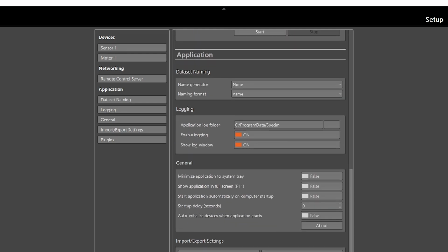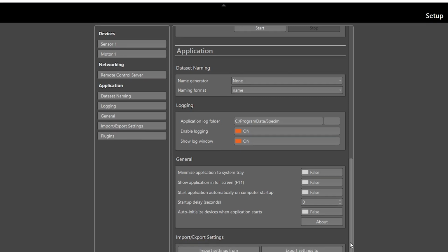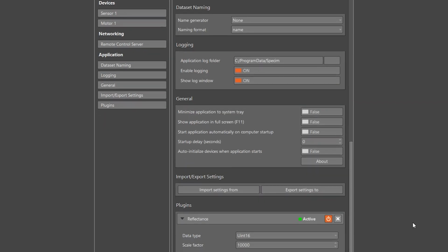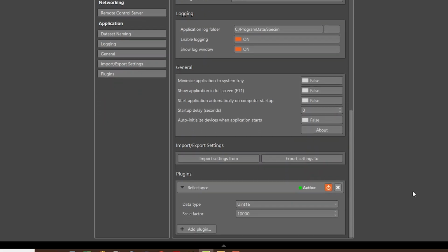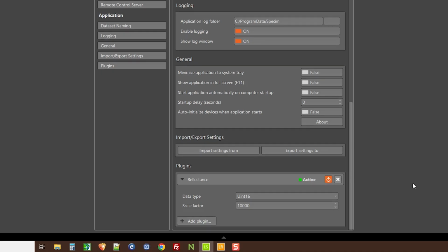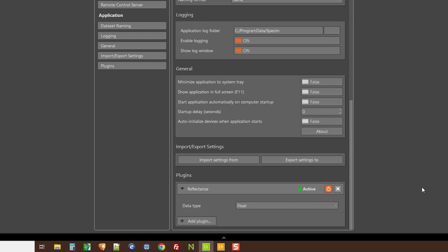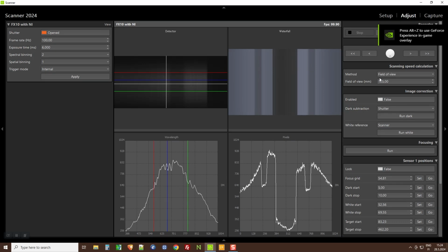Also, keep in mind that the software, Lumo Scanner and Recorder, by default records only dark and white references and the raw data, of course, but it doesn't record the reflectance data. For the reflectance data, we have a plugin like here, and we can choose to have, for example, the reflectance data recorded in float or calculated in float. We have different types of plugins, for example for radiance or time-lapse, things like this. But now we move to the more interesting page.